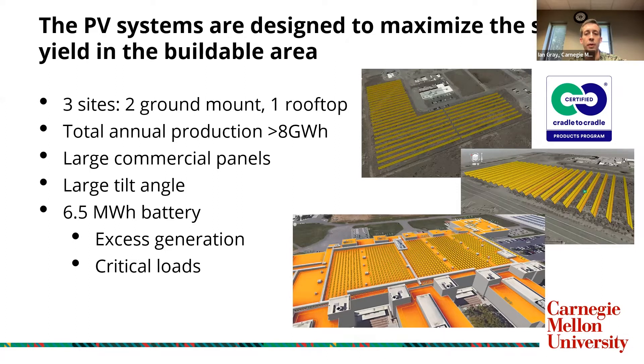470-watt commercial modules were chosen from SunPower, now Maxeon, due to their high efficiency of almost 22 percent, low degradation guarantee of less than a quarter percent per year over their 25-year life, and cradle-to-cradle silver certification — they're very circular and highly recyclable at the end of their life. We chose these larger modules to reduce the total module count and the associated installation and mounting hardware costs.